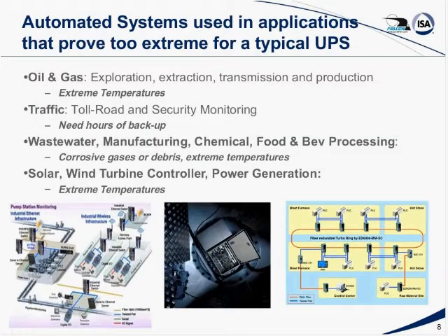Okay, so then Mike, could you give us some examples where automated systems may be in environments that are too harsh for a typical UPS? Yes. Typical application, oil and gas exploration. SCADA is used exclusively on gas and oil pipelines. It's used for monitoring and management of the pipeline. And these pipelines are, of course, in all types of environments, everything from the North Slope in Alaska down to the deserts of Texas. The SCADA systems provide critical monitoring on these pipelines. It's an issue of monitoring the flow, the rate, and also safety issues. And it's extremely important that the SCADA system be up 100% of the time.